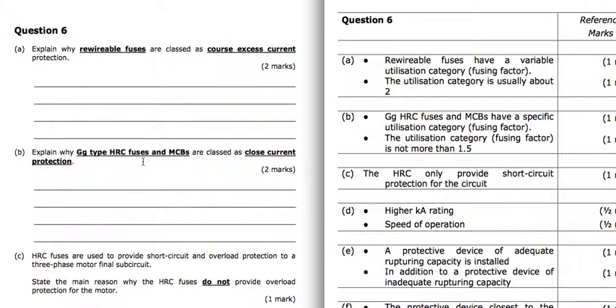HRC fuses and MCBs are close current protection. And why are they close current protection? Because their fusing factor, or the utilization category, is not more than 1.5. So they give us much closer protection. If it's a 10 amp fuse, we know it's going to blow before it gets to 15, or when it gets to 15. If it was a rewirable fuse, it might take until 20. So rewirable is coarse current protection; MCBs and gG HRC fuses are close.